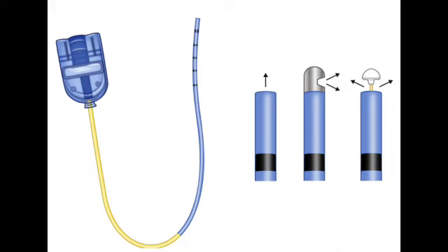All right, let's get into the mechanics. You called it non-contact thermal therapy. How does that actually work? How do you heat tissue without touching it? Yeah, it's pretty clever. The APC system uses a special catheter that delivers two things simultaneously. Argon gas. Okay, just plain argon. Yep, inert argon gas. And it delivers a monopolar electrical current through a wire inside that catheter. Monopolar, meaning the electricity needs a path back, right? Exactly. We'll come back to that. But the key is what happens at the tip.